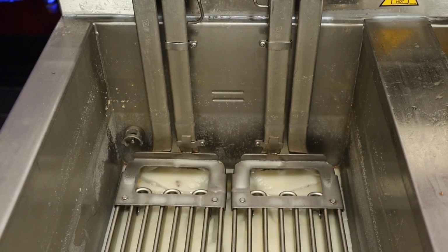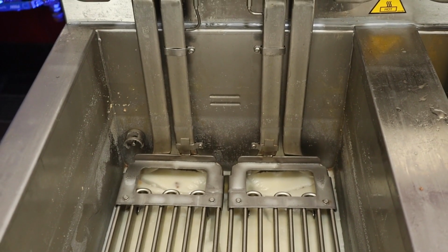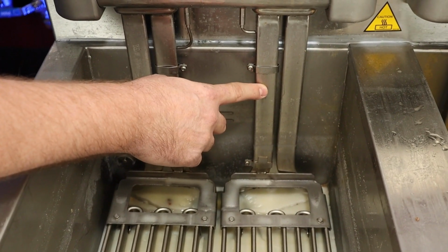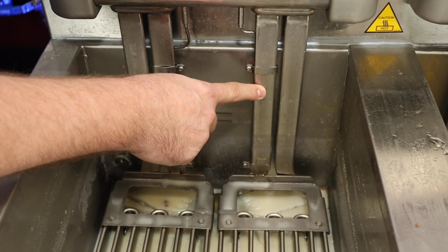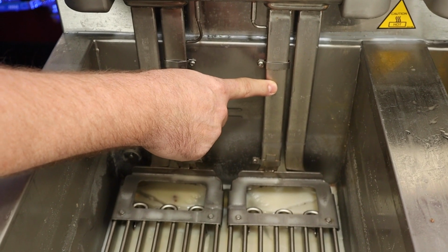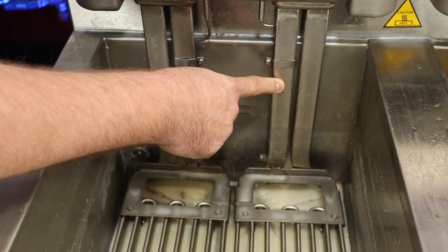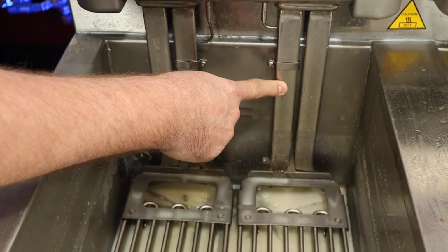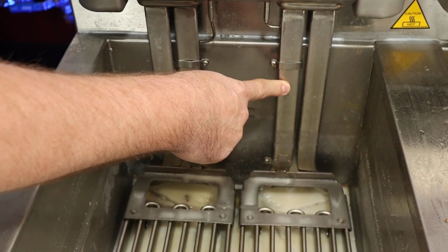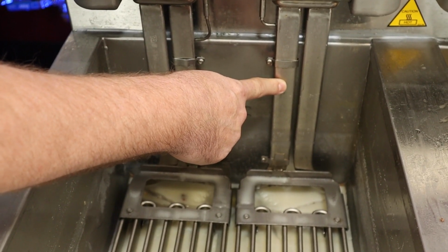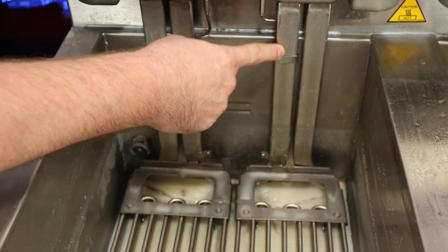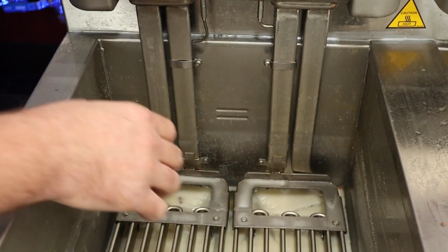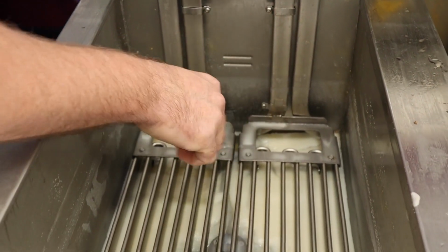So what it looks like to troubleshoot that is we could actually have maybe a bad high limit probe, and we can go ahead and check resistance with our meter at the high limit PCB where the high limit probe connectors plug in. And what we can do is check for calibration and check resistance to see if this probe is working properly.